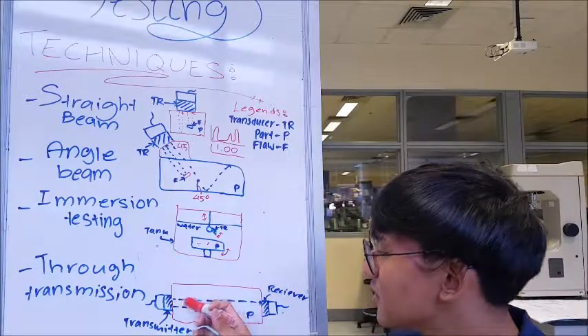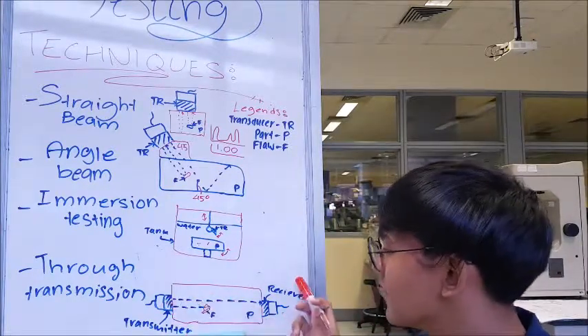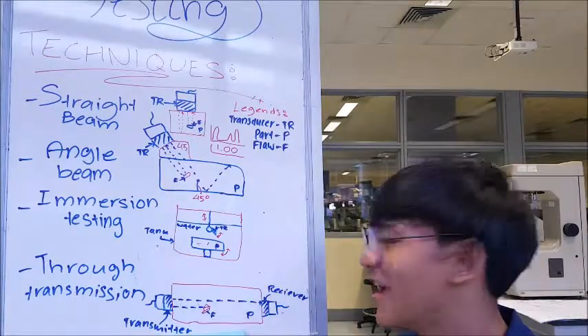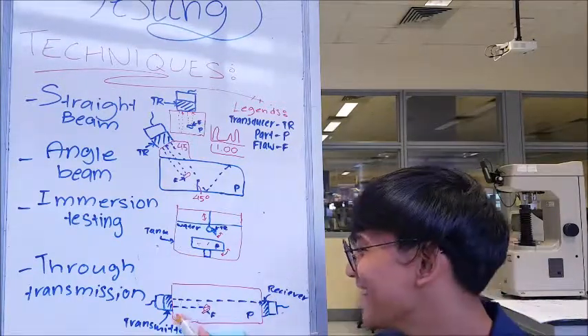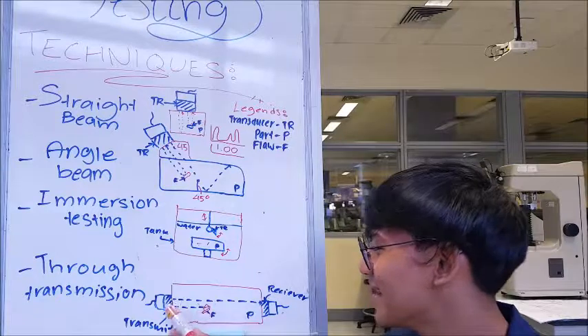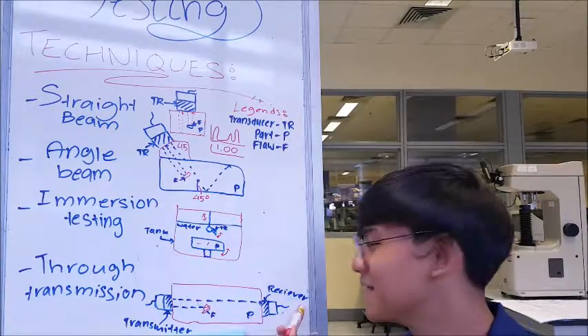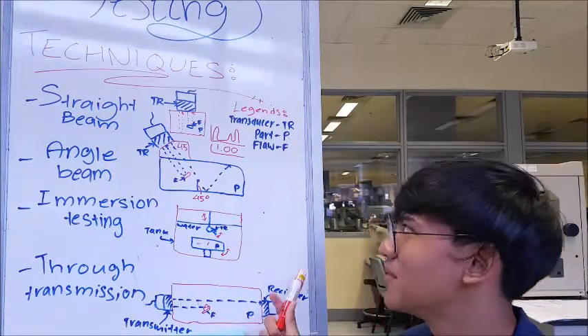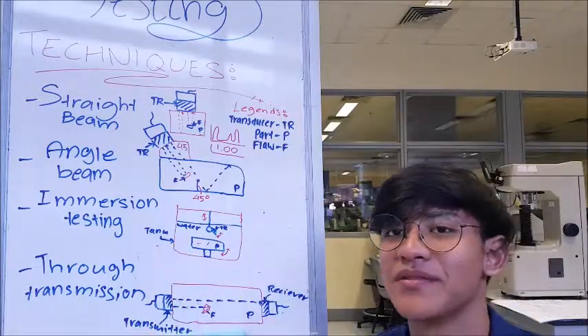Through transmission, unlike the others, uses a transmitter and a receiver instead of just a transducer. If sound energy is introduced from the transmitter, it will be received by the receiver on the receiving end. Tongue twister. If a flaw is present, less sound energy is received by the receiver, and it will be displayed on the screen as a lower amplitude.